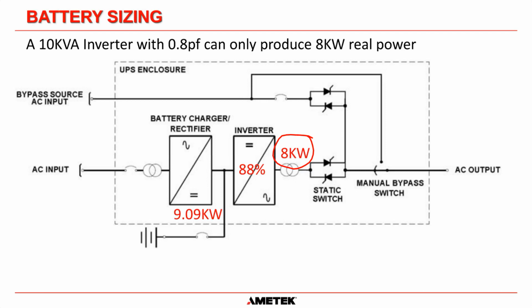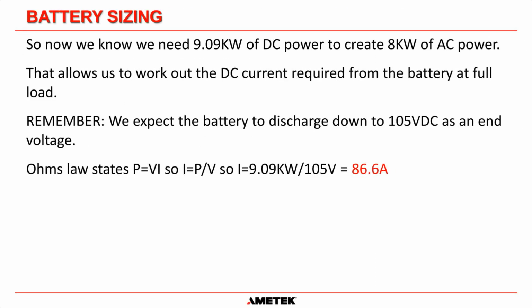Okay. But then our inverter is only 88% efficient. And I got that from the DPP spec sheet. So all the engineers should know from our spec sheet what the inverter efficiency should be. And ours is 88%. So therefore, you divide 8 kilowatts by 0.88, and you get this number here. You need 9.09 kilowatts DC power into the inverter to be able to overcome losses and put out 8 kilowatts. Hopefully that's clear. So we need 9.09 kilowatts to generate 8 kilowatts of AC power. So now we know that.